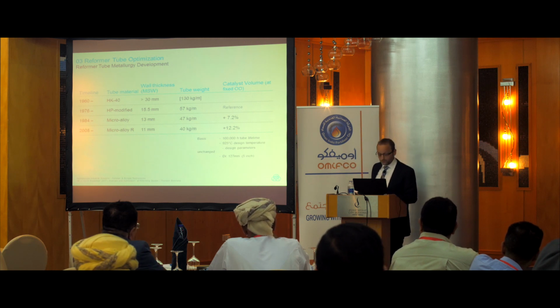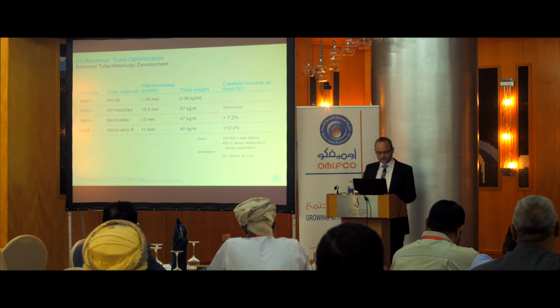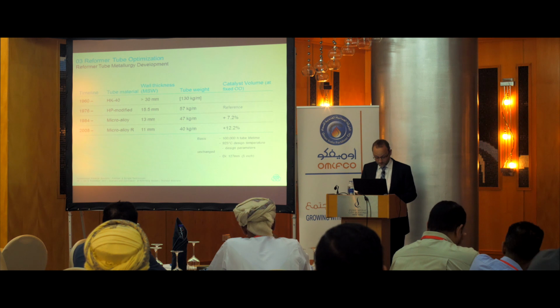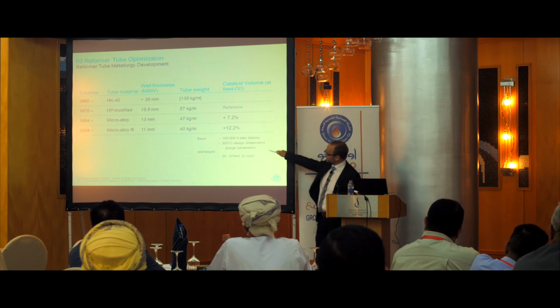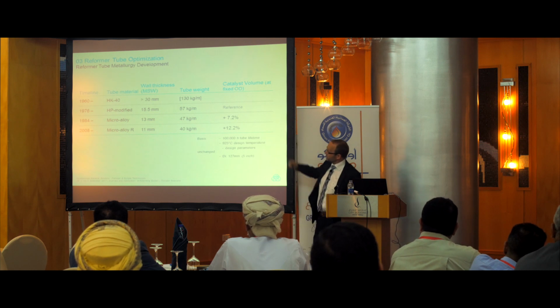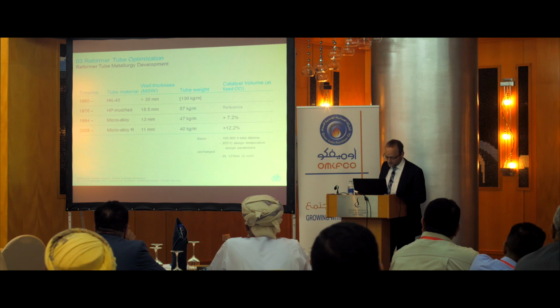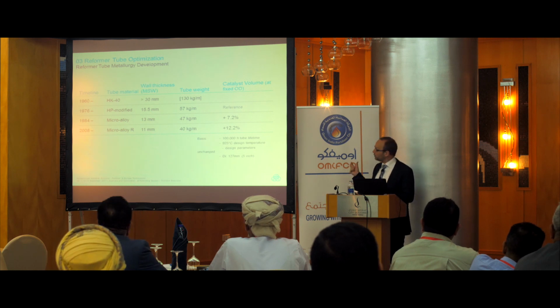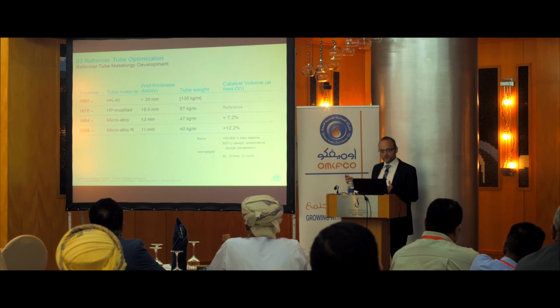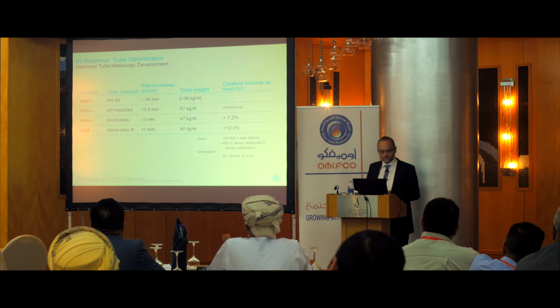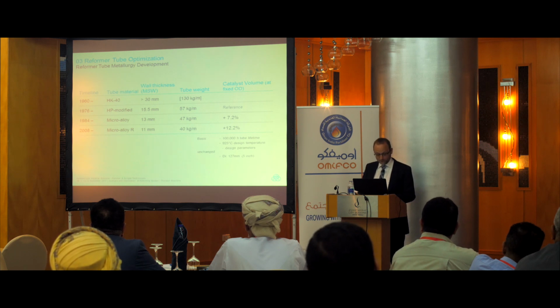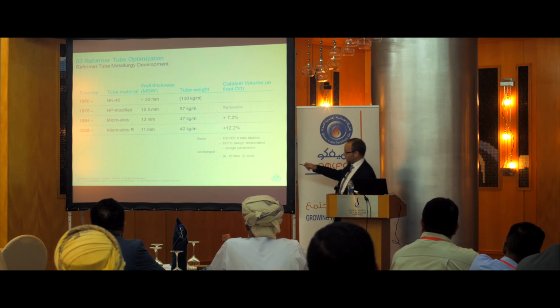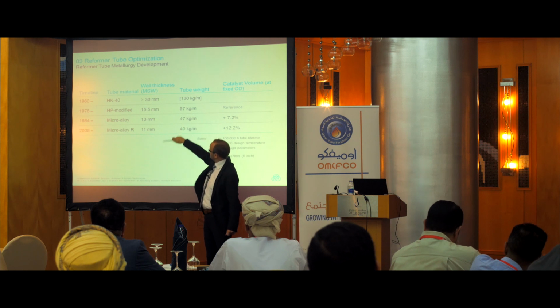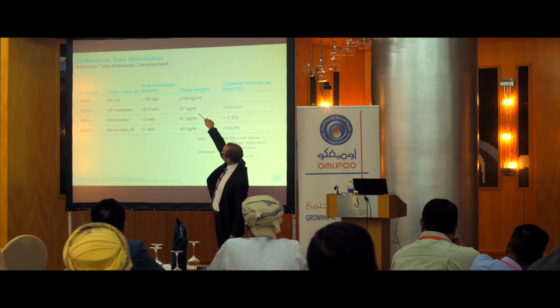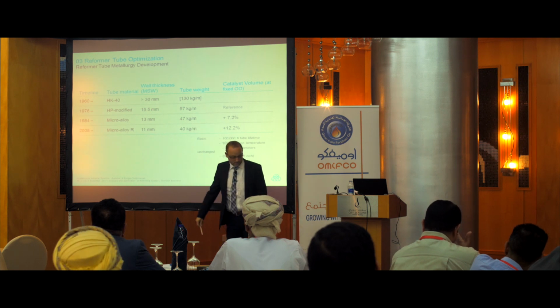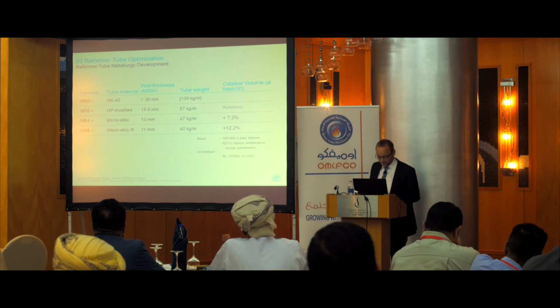So with these data, we computed an example which shows the effect of the higher creep rupture strength. First of all, with the calculated design data which we are using today, an HK40 tube would have more than 30 millimeter wall thickness. But that is just a theoretical value, because 30 millimeter wall thickness you cannot cast, and the thermal stresses within the wall would be too high, and that would limit the tube life dramatically. Interesting is the thickness reduction from HP to microalloy R from around 15 to 16 to 11. And with this, of course, the decrease of tube weight. And this would result, of course, in a huge cost saving.